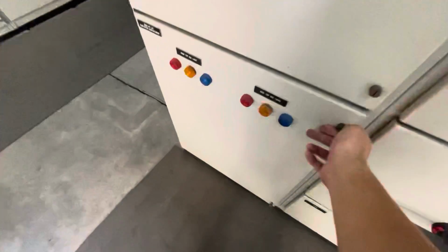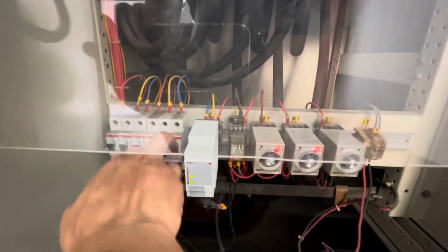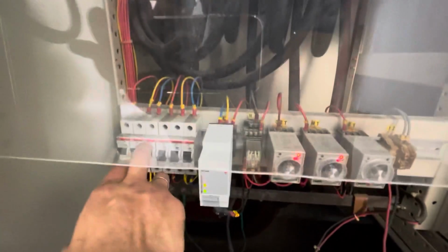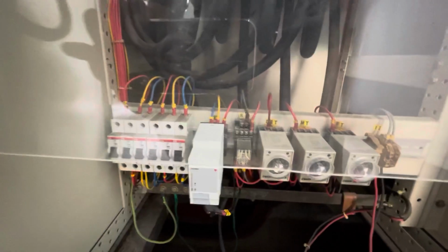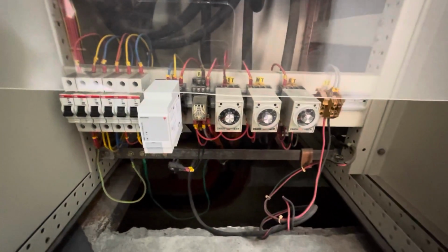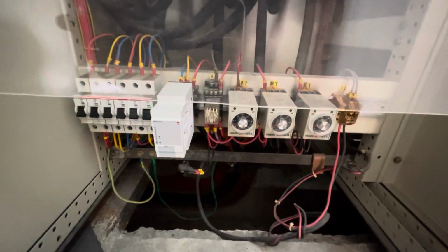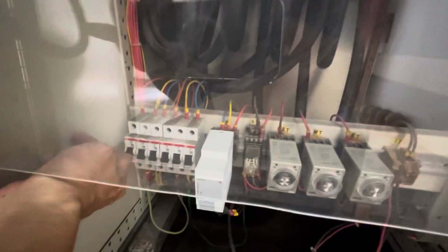Okay, this is the EMSP panel. As usual, we're going to test exactly the same. It's just that this round, the genset is just beside this room, so we can definitely hear the sound when the genset runs. First of all, off the genset MCB first, then off the main supply MCB. Then we wait for the genset to start. Okay, the genset is starting already. Once it starts, we on back the main supply MCB first. Alright, then only we on the genset MCB.